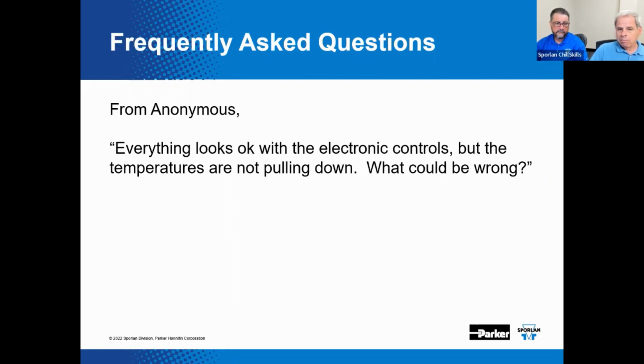Make sure that any system service valves, such as ball valves and hand valves, are open. Make sure that the liquid filter dryers are not running high differential pressures. And if they were, what would that mean? That would mean that they have done their job and caught a bunch of debris, and it's time to change them. So you don't want any dirty or clogged strainers, and that can certainly be an issue on an initial system startup. I guess that just goes to say, much of our S3C tech support seems to be dedicated to resolving basic refrigeration system issues and delivering the accompanying resolutions, which is part of what we do. Yep, it is. That's a lot of the questions that team gets.